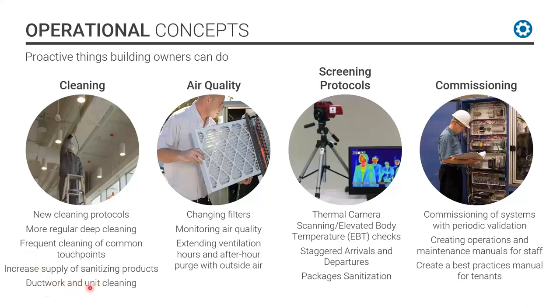Ductwork and unit cleaning for buildings that have been sitting idle for 6 months, if there are any, we want to get in and clean the units out. Changing filters, monitoring air quality, extending the hours of operation, I mentioned 2 hours before and 2 hours after. Screening protocols, when you come in the building, are they going to be taking temperatures of people? Are you staggering hours of arrival and departure? And packages, everybody was flipped out, I'll use that term, in March about touching surfaces. Now people are less concerned. It's still good to be vigilant, keep surfaces clean and wash your hands. And are we going to allow packages to come in the building? There has to be an approach.